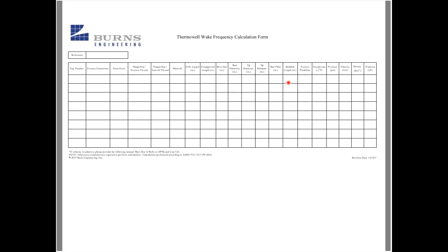Typically the items that you would need to fill out would be highlighted in some fashion. Send that back to the manufacturer, and they can go ahead and run the calculations, and then they'll develop a form that says, based on this set of conditions, your thermowell either passed or it did not pass. And if it didn't pass, they'll make some recommendations as to how that thermowell design can be changed so that it does pass.